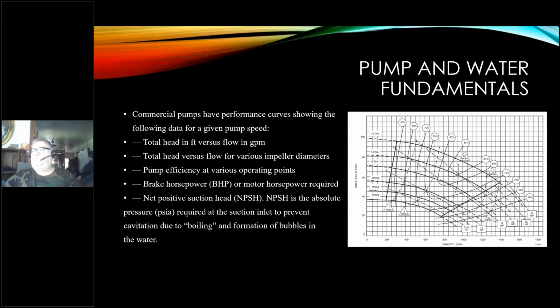If you don't do that, and you're in a closed system, basically where you're not able to pull air in, you will actually cause a vacuum in the suction of the pump and boil the water. You reduce the atmospheric pressure to the point that the water will boil inside the pump. Now, I've actually had this happen more than once, and I'm ashamed to say that, because a lot of people will have problems with pumping, and the first thing I look for is, do we have the right amount of water coming into the pump?